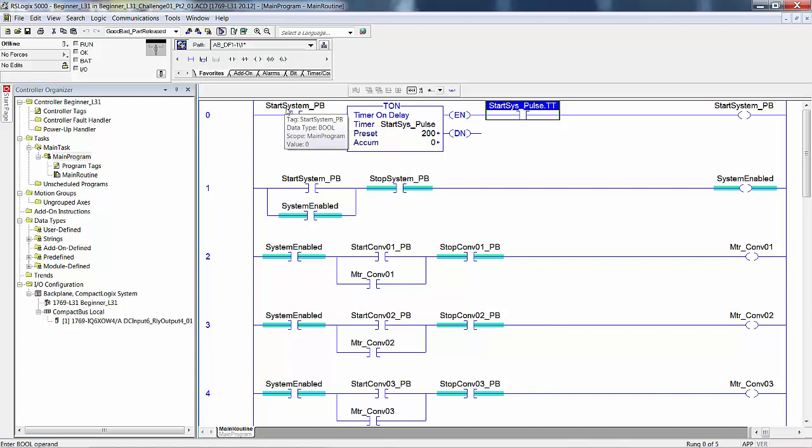We turn that bit on and the rung turns that bit back off. So it's self-extinguishing. This is a nice little piece of logic to tuck away in your toolbox. You might need it someday. And then it comes back to rest as shown. So this is at rest here. Simulating a momentary stop push button.